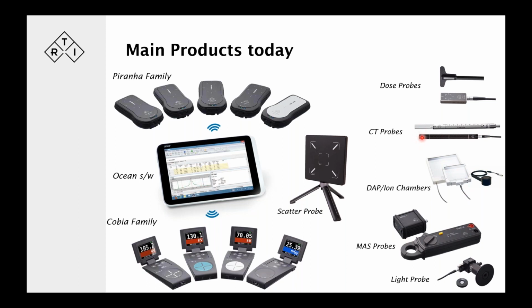CT probes as well, the normal CT ion chamber, that's 100 millimeters. There's a bigger one also, 300 millimeter, that covers the wide beam CT measurements. The CT dose profiler looks like an ion chamber, but as a matter of fact, it's a solid state detector with a single point detector here, where you can use that to measure the beam width. The detector itself is 0.25 millimeters big, so you poke that through the CT beam and sample the dose. And if you know the speed of travel, you can recreate the dose profile of the complete X-ray beam.